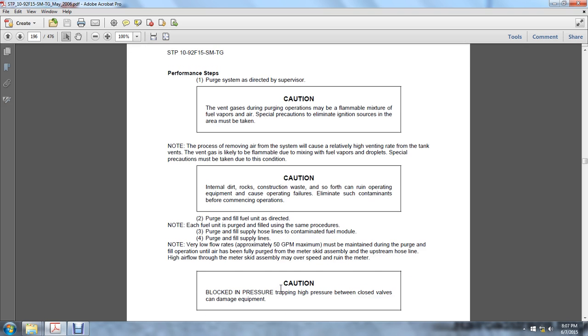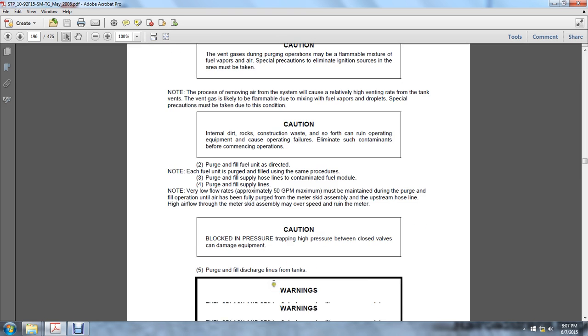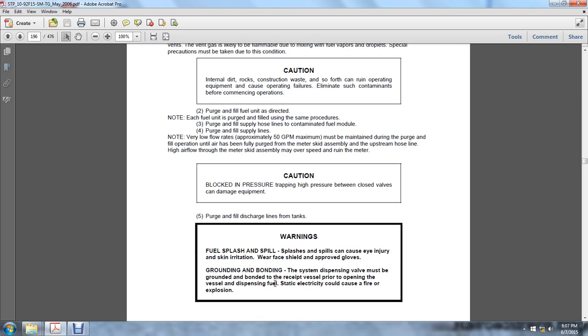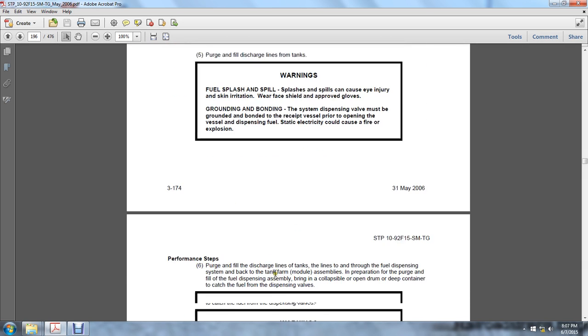Caution: blocking pressure, trapping high pressure between closed valves can damage equipment. 5. Purge all fuel discharge lines from the tank. Warning: fuel splashes and spills can cause eye injury and skin irritation. Wear face shield and approved goggles. Grounding and bonding: the system dispensing valve must be grounded and bonded to the receiving vessel prior to the opening of the vessel. Dispensing of the fuel, static electricity could cause a fire or explosion.